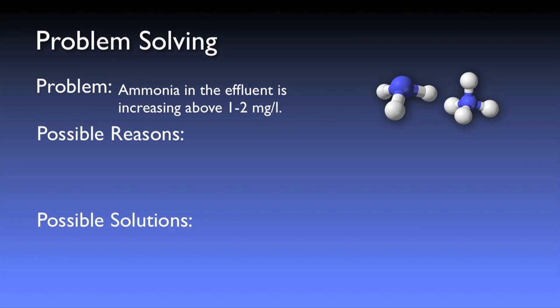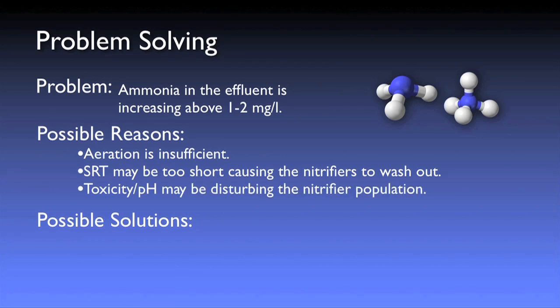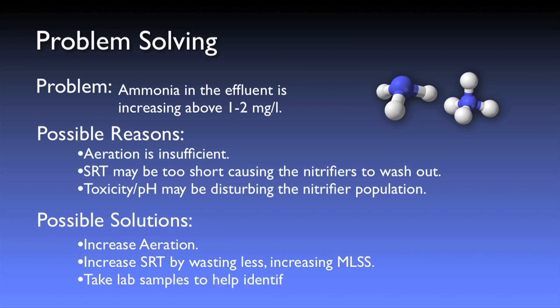We know that nitrification is an oxygen-hungry process — perhaps the aeration is insufficient. We also know that nitrifiers grow more slowly, so perhaps the SRT is too short due to an influence of temperature. And we know that nitrifiers are very sensitive to changes in pH or toxic conditions, so perhaps this performance loss is due to a disturbance of that nature. If low DO is the culprit, full nitrification will return by increasing aeration. If temperatures have dropped, the SRT may need to be increased to maintain a healthy nitrifying population. If pH or toxicity is the culprit, certain specific actions may be required depending on the exact cause.